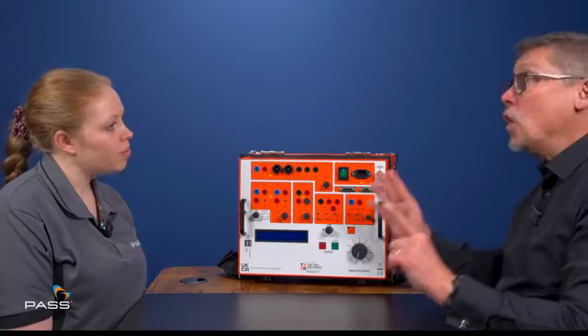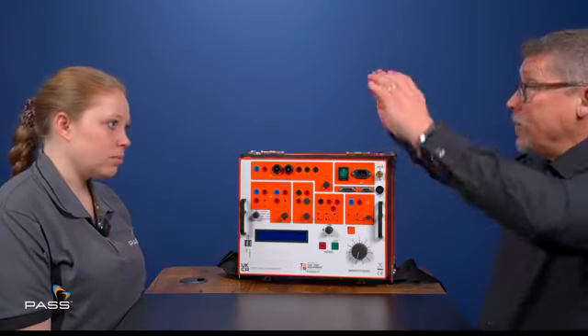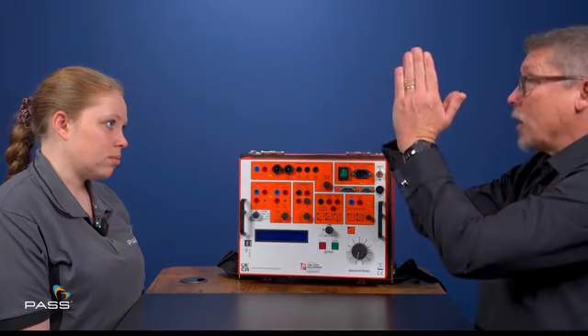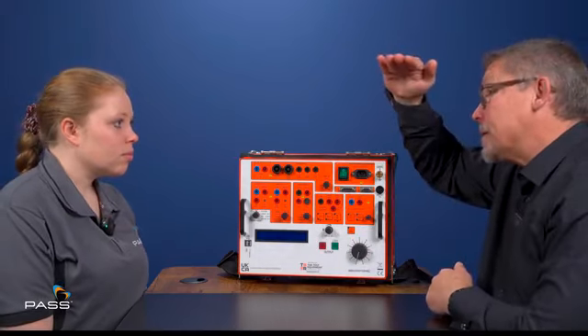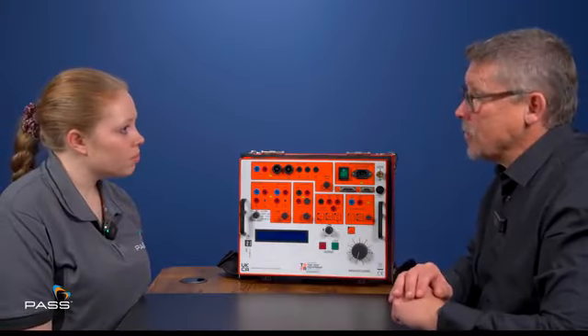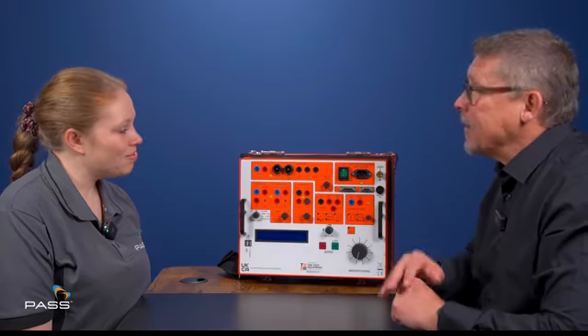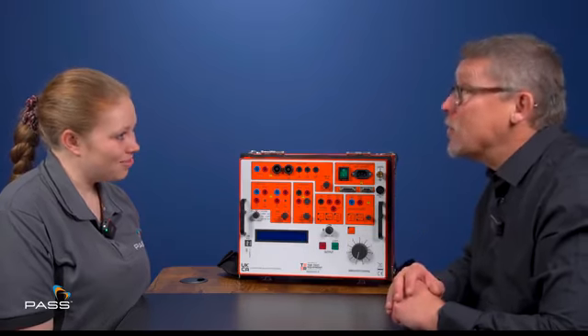You can then look at the waveform, because all relays are designed to work on a sine wave. If it's not a sine wave, for example, if your waveform that should be like that goes more pointy and thin, but still hits the peak of the current, what you've got is not as much energy going in. So a relay that should test in 5 seconds, for example, might test in 7 seconds. So before you return all those relays to the manufacturer and then get charged for returning relays that are not faulty, you can check the waveform and make sure that that is actually okay.